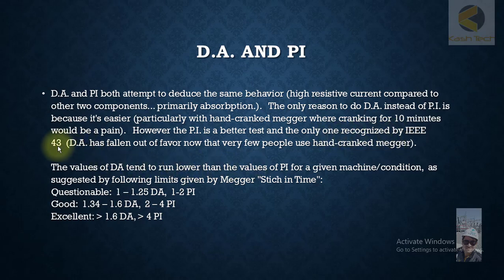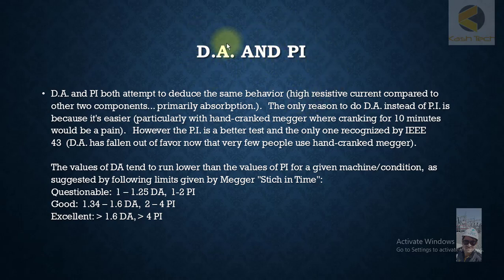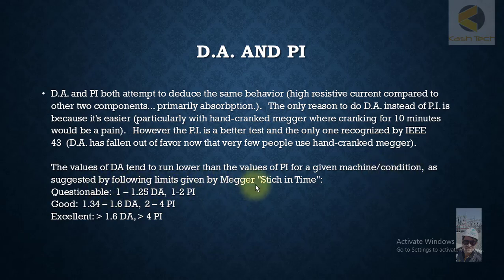DA has fallen out of favor now that very few people use hand crank meggers. IEEE supports basically the testing of PI; DA is not acceptable for them. The values of DA tend to run lower than the values of PI for a given machine or condition, as suggested by the following limits.